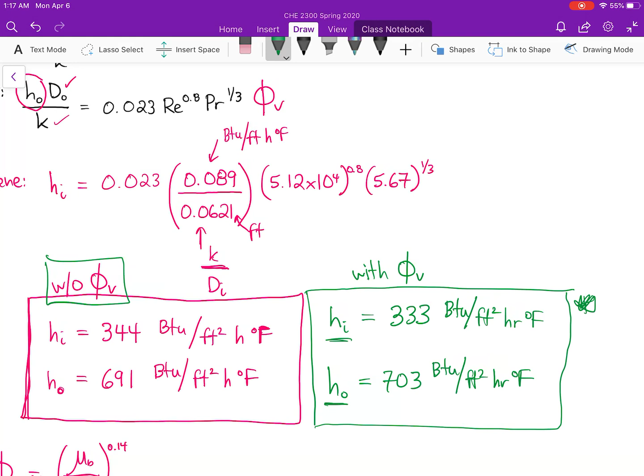The last part of our problem asks us to calculate an overall heat transfer coefficient based on the outside surface area of the inner pipe. So let's go ahead and do that. We know that our overall heat transfer coefficient is equal to 1 over, in this case we're basing it on the outside area, times the sum of our thermal resistances. So for our particular scenario, what does this equation look like? We have 1 over hi. That's multiplied by the ratio of our diameters on the outside and inside, plus the resistance due to the wall.